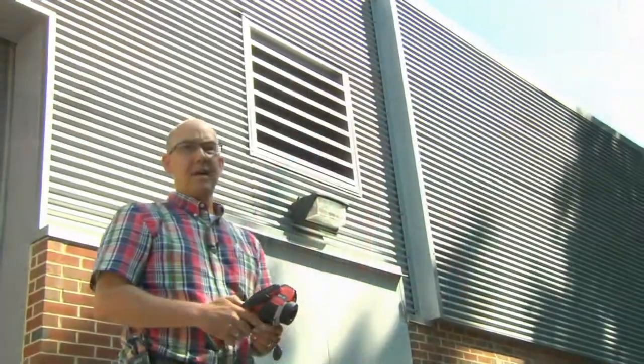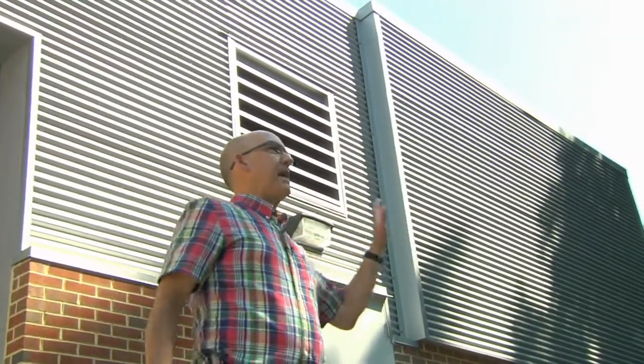Do I have any outdoor condensers? If I've got split cooling systems or air-cooled chillers, not necessarily this building, but other buildings, if they're on grassy areas, is that grass, the clippings, are they collecting up underneath on the coils? So those are some of the things that we want to look at. Okay, so what we want to talk about is exhaust fan.